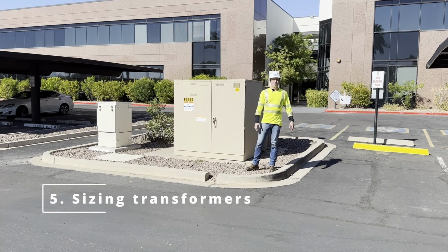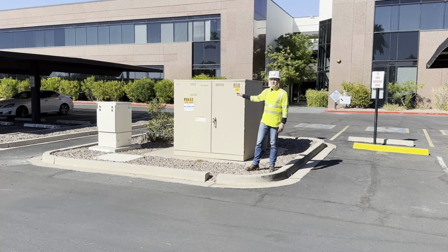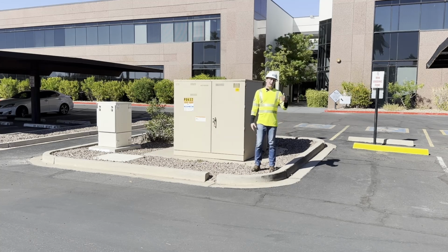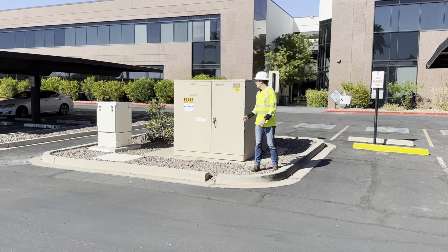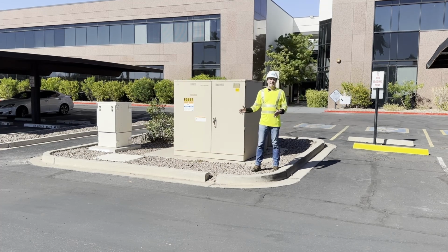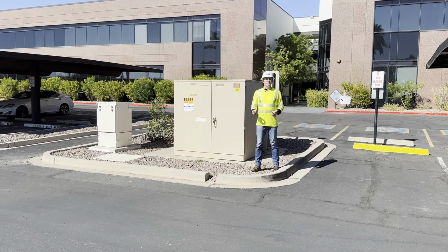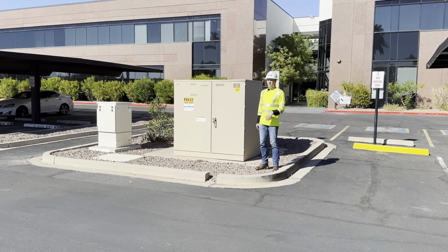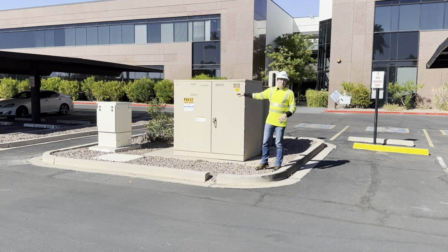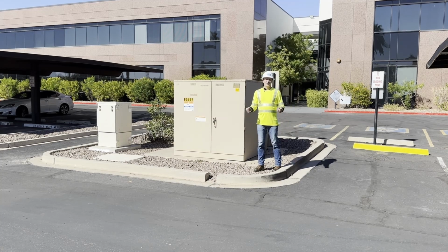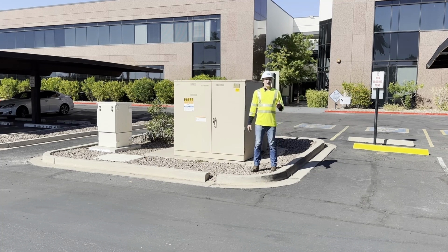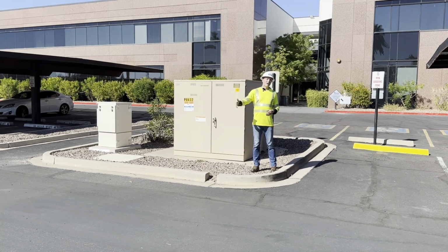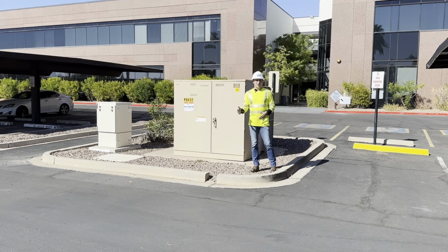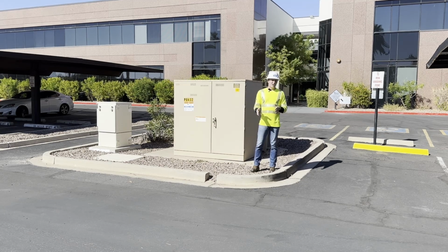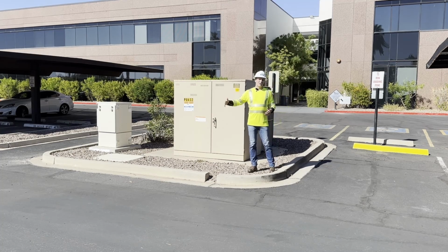All right, so number 5, we're going to talk about sizing transformers. The size of a transformer is very important for your EV charging project, to match your load as best as possible from the utility side. Transformers are sized in what's called kVA, and we're not going to talk about the specifics of that in this video, but in future ones we'll get into all the weeds of that. But for 120/240 transformers that you'll see for residential and commercial, those are sized between 25 kVA and about 167. 120/208 volt, 3-phase, that'll go from roughly 150 up to about 1500 kVA.